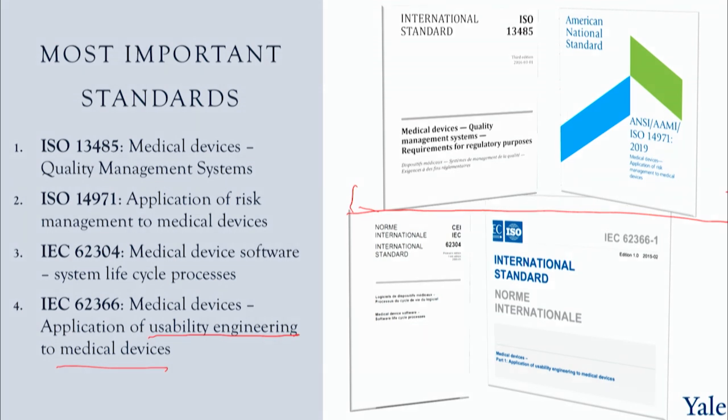The standards may not be 100% in fulfilling the needs for a particular jurisdiction. So ISO 13485, as we'll talk later, is not one-for-one the same as what the FDA would look for in a quality system, but it's close and it gets you most of the way there.